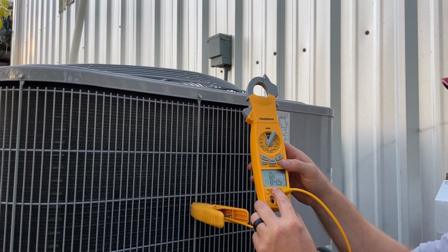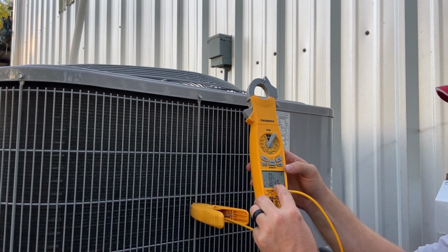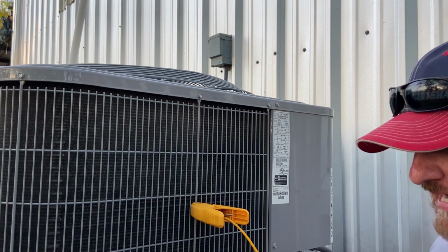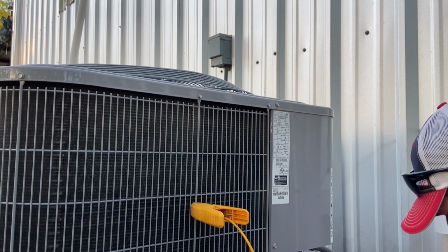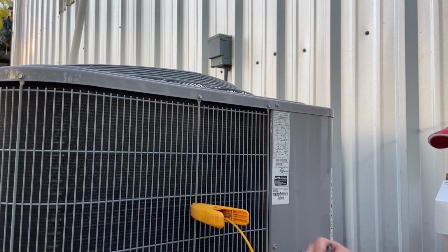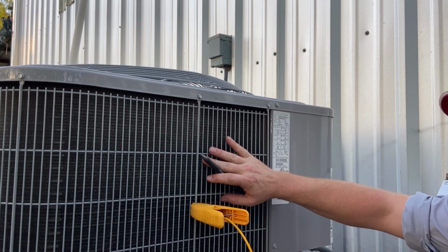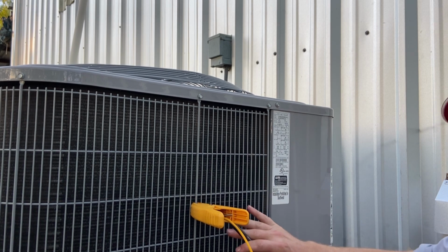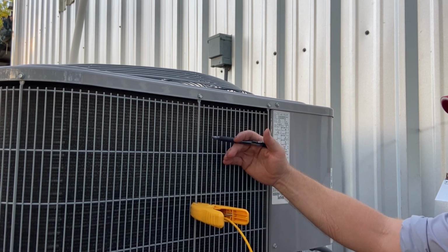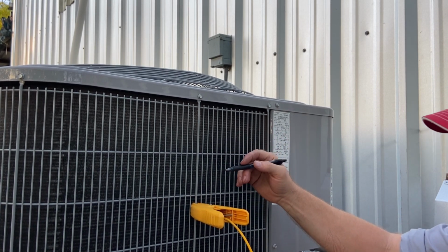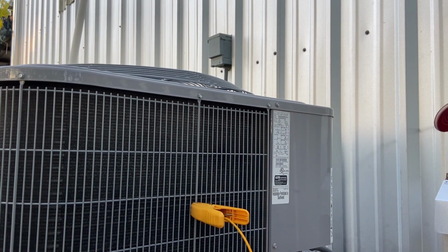And our air temperature is 84.5, so we're running up to 85. So we figure we have 99 minus 85, that gives us a TD of 14 degrees. My saturated temperature is 14 degrees over my ambient temperature. The saturated temperature is 14 degrees warmer than the temperature of the air coming into the unit.